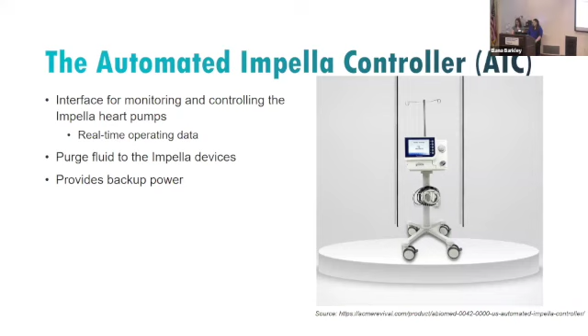Here's an image of the automated Impella controller for the Impella CP and 5.5. The red line here is the aortic waveform. The white line is the left ventricle pressure, and the green is your motor current. And on the bottom of the screen, it shows your Impella flow, current purge flow and purge pressure, cardiac output, and cardiac power output.